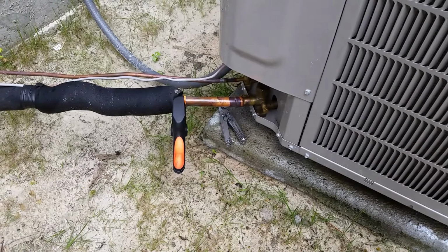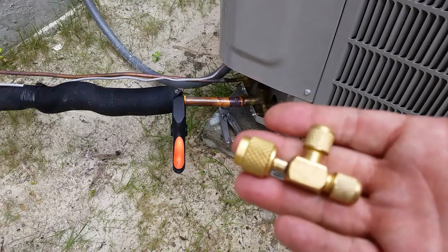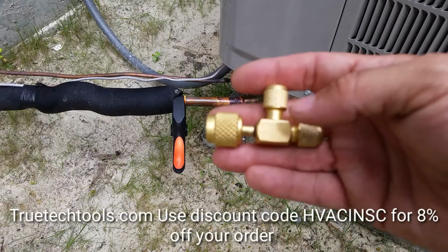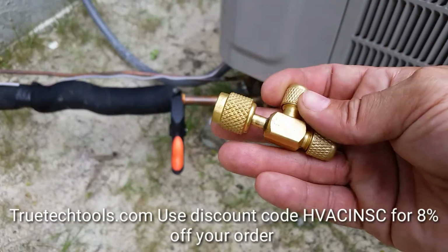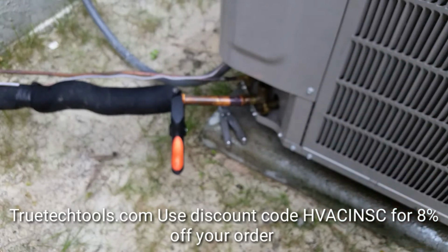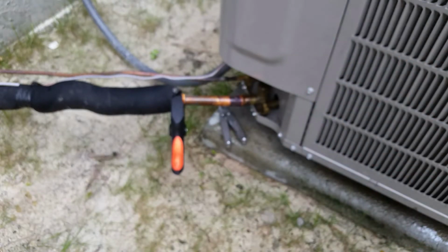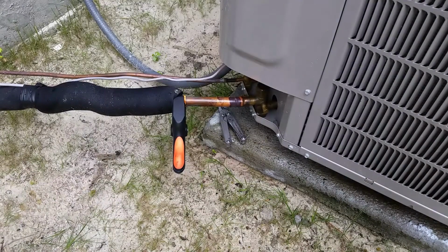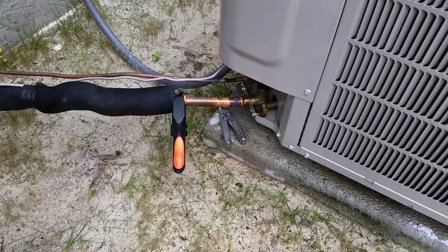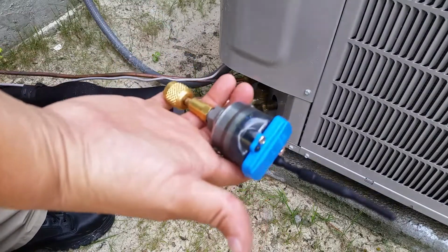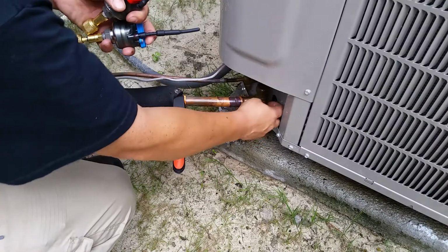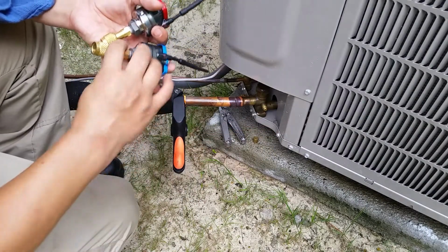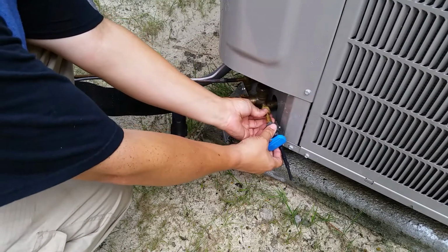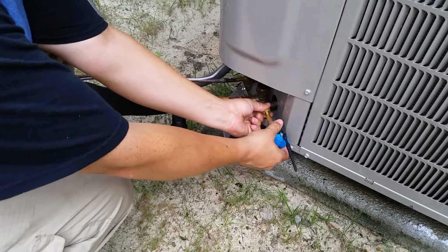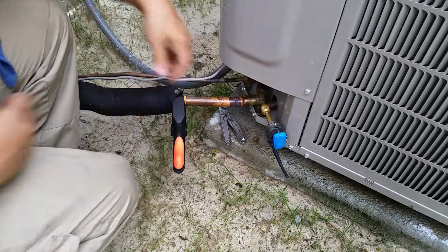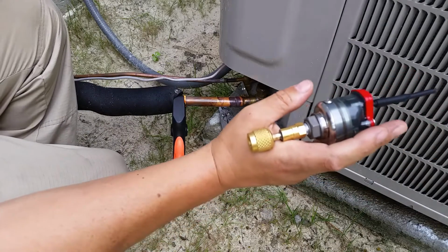And again, a good thing to add to your probes is a finger tight swivel tee. You can get these from TruTech Tools. You can get 2 of them for around $20, made by CPS. Come in handy for charging, adding, removing refrigerant, and also difficult access refrigerant ports. But we'll go ahead and hook them up. Got our low pressure transducer. Our high pressure transducer.